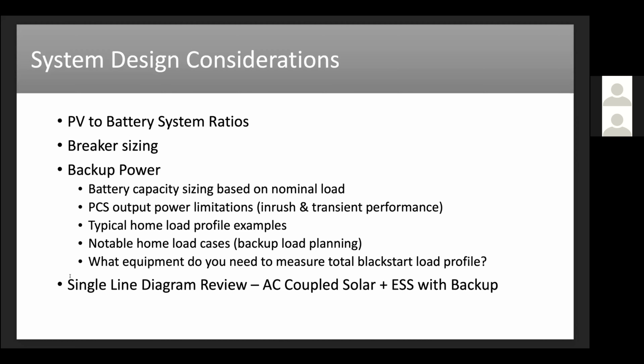Okay, let's look at some system design considerations. What we're going to look at in the next few slides are the PV to battery system ratios. We'll look at breaker sizing for your interconnection, backup power, battery capacity sizing based on a nominal load, and PCS output power limitations for both inrush as well as transient performance. We'll look at some typical home load profile examples and some notable home load cases as well for backup load planning. Really important there, and this is a really important step, is planning your backup loads panel.